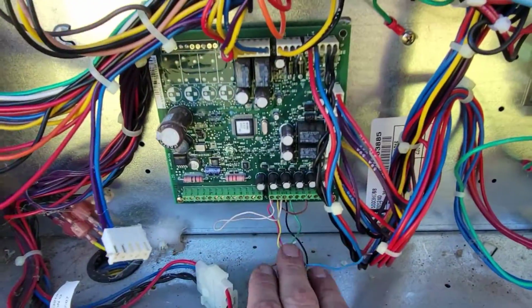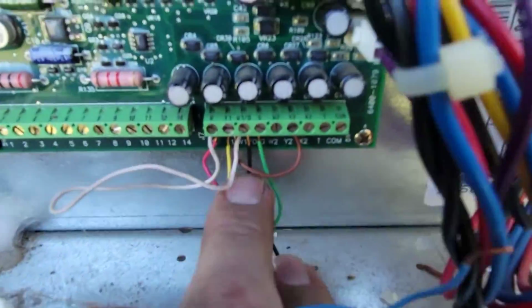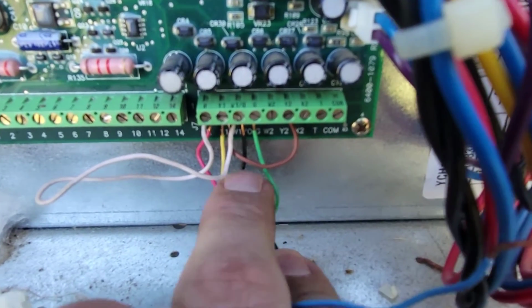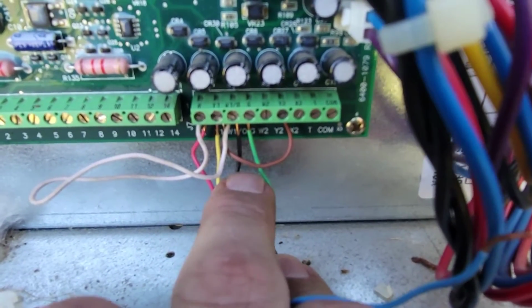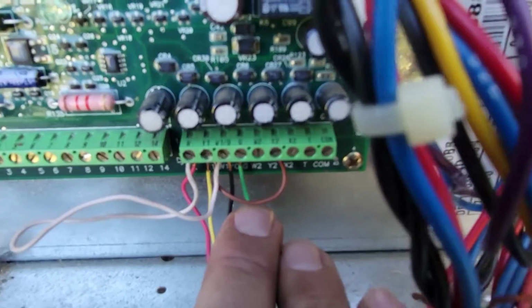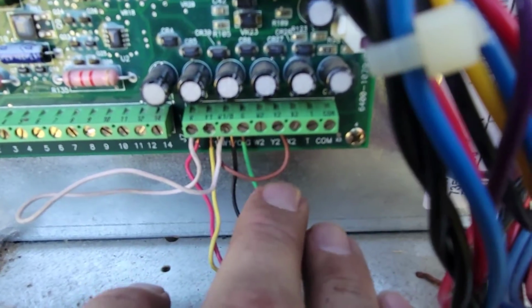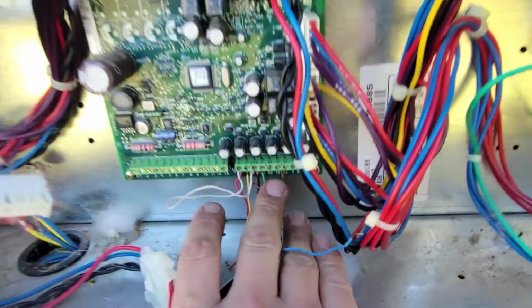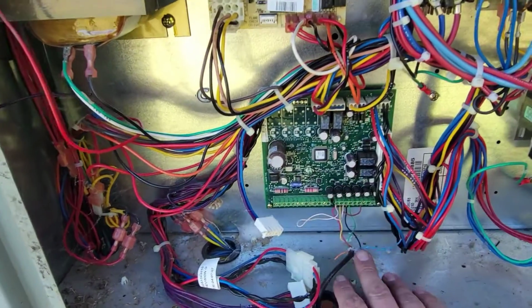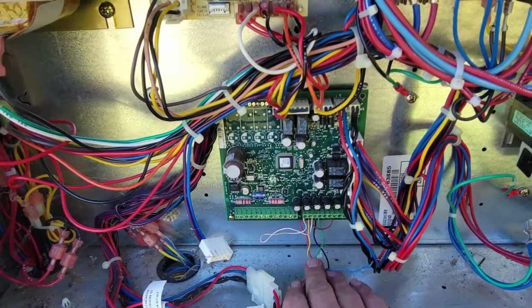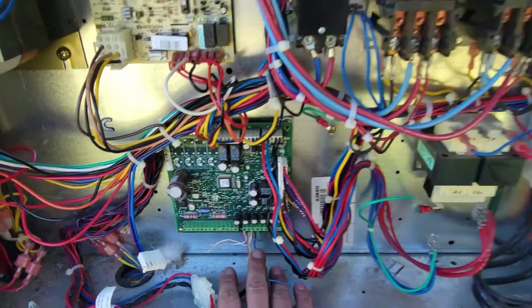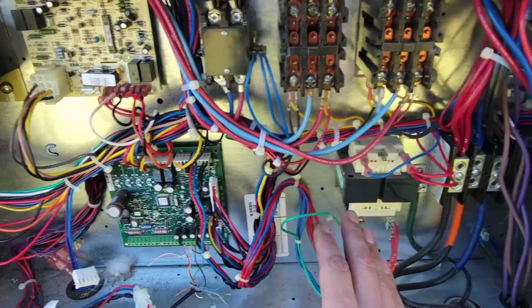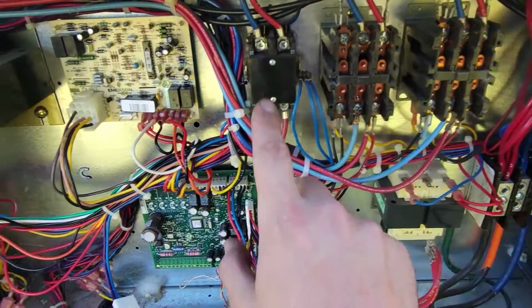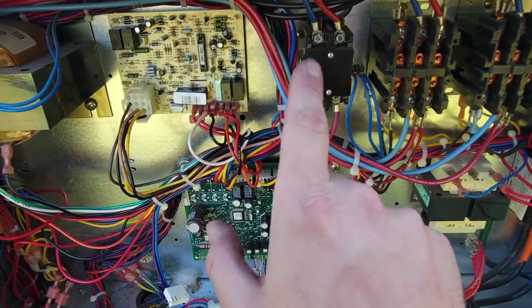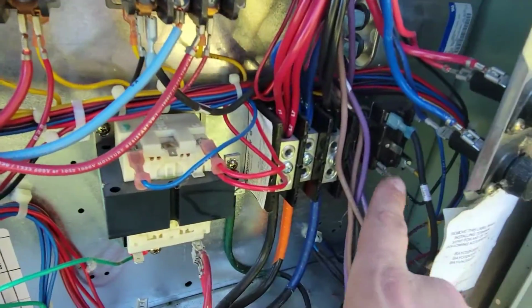So this right here is where the 24 volt connections come in. We've got our red, yellow, so we got our Y1, W1, this is our call for heat. We got G, W2, which is second stage heat if you got it, Y2, second stage cooling. This right here is where our low voltage thermostat wiring comes into our package unit. Okay, we got transformers, we got two contactors for our compressors, contactor for our indoor fan. This right here is the relay for our outdoor fan.